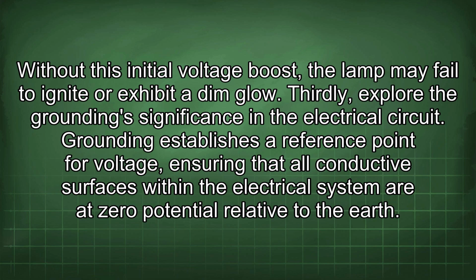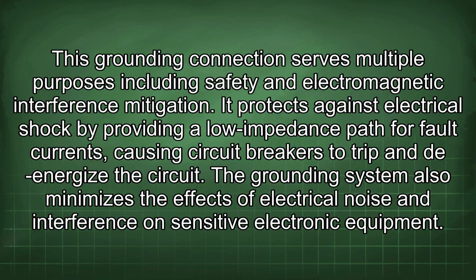Thirdly, explore the grounding significance in the electrical circuit. Grounding establishes a reference point for voltage, ensuring that all conductive surfaces within the electrical system are at zero potential relative to the earth. This grounding connection serves multiple purposes, including safety and electromagnetic interference mitigation. It protects against electrical shock by providing a low impedance path for fault currents, causing circuit breakers to trip and de-energize the circuit. The grounding system also minimizes the effects of electrical noise and interference on sensitive electronic equipment.